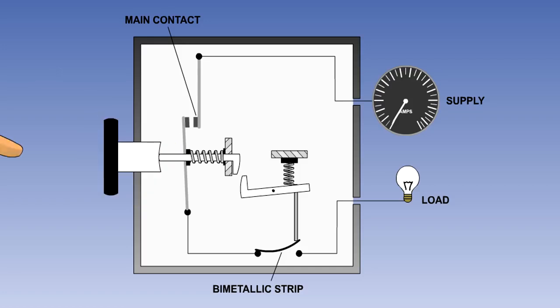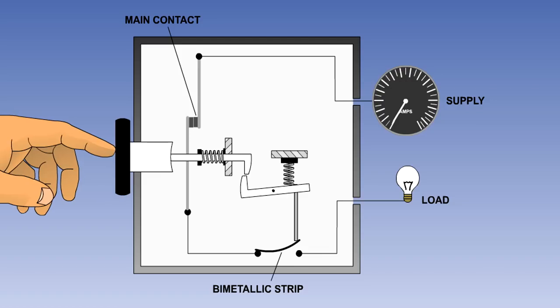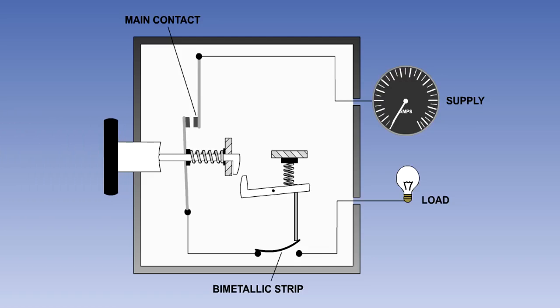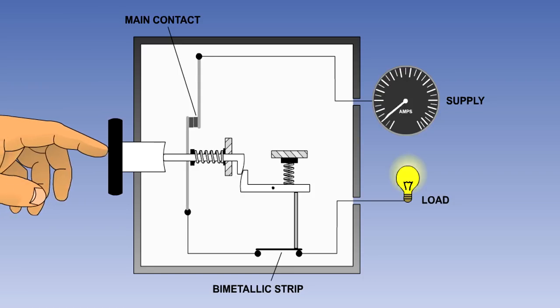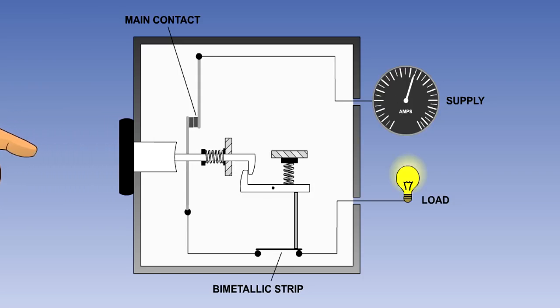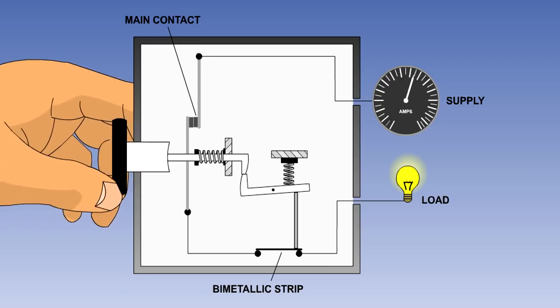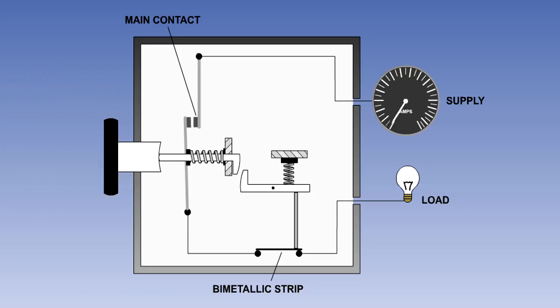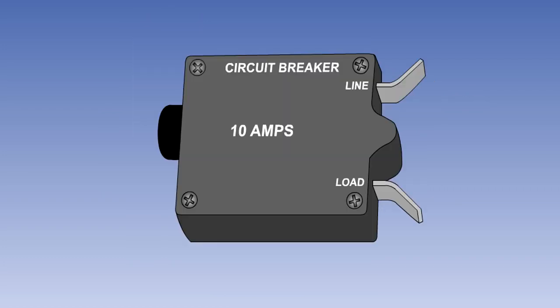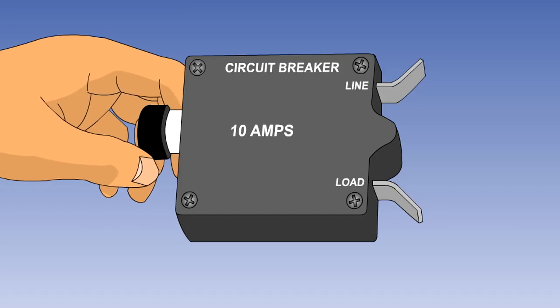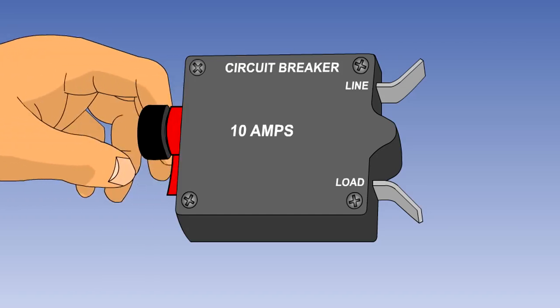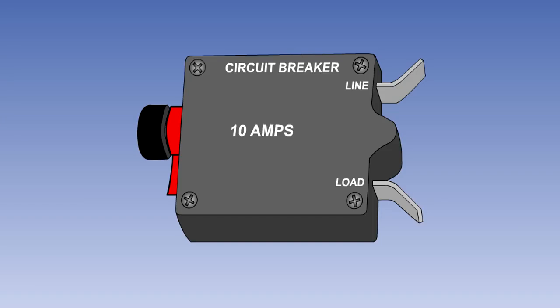If an immediate reset attempt is made, the current will not flow in the circuit, because the bimetallic strip contacts will still be open, and the button will not latch in. Only when the bimetallic strip has cooled sufficiently will the circuit be able to be completed again. This type of circuit breaker can be used as a switch by pulling out the button. This will override the latch mechanism and open the main contacts. If a circuit breaker has been pulled for maintenance purposes, then a clip with a red flag attached is affixed to the shank to warn personnel not to reset it.